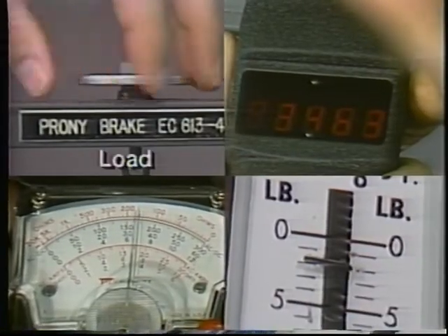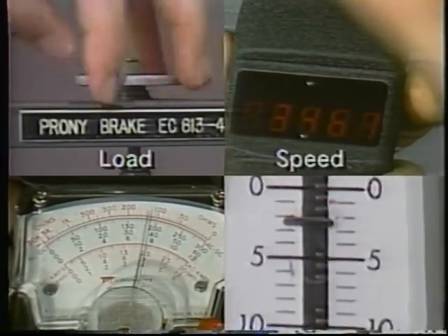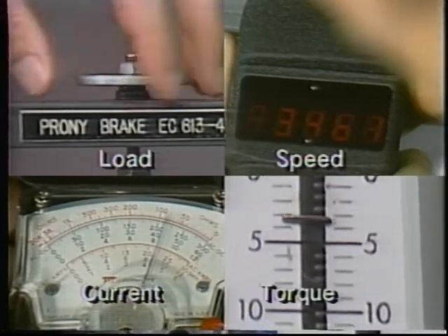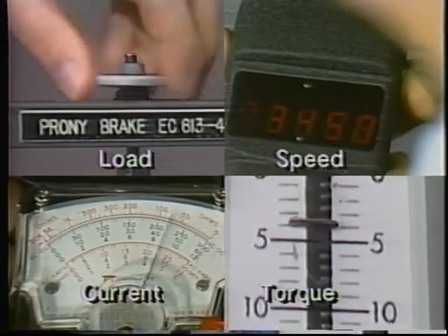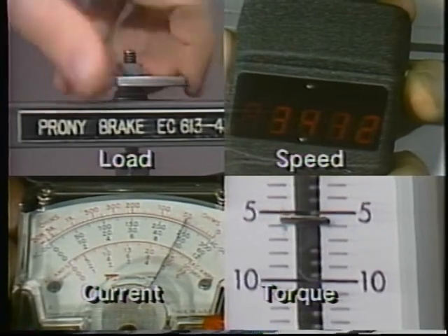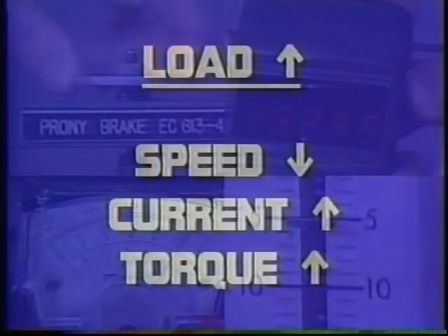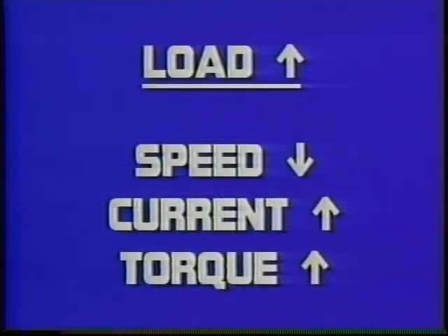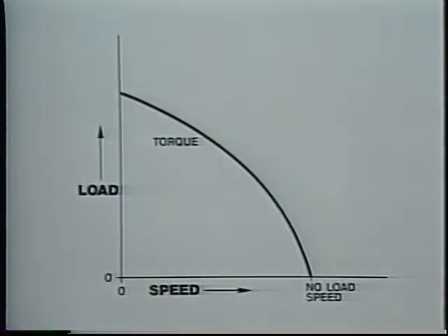Most motors will slow down when a load is applied. The greater the load, the slower the speed, and the greater the current and torque. This basic relationship between load, speed, current, and torque is important to keep in mind — particularly when troubleshooting motors. We will see it applied frequently in later lessons.